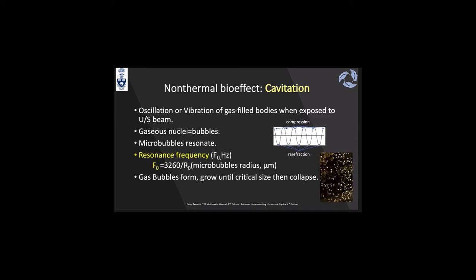The second non-thermal bio effect is cavitation — a topic they love to ask about. Cavitation is oscillation or vibration of gas-filled bodies when exposed to the ultrasound beam. During the push wave of the ultrasound beam, there is rarefaction and compression of the bubbles — also referred to as gaseous nuclei. The microbubbles resonate at a resonant frequency F0, calculated as 3260 divided by R0, where R0 is the microbubble radius in micrometers. The gas bubbles oscillate, grow until they reach a critical size, and then collapse — that is what cavitation is.